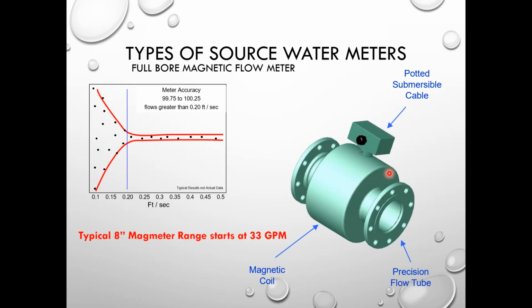So this screen shows our typical mag meter, and these are probably the most popular meter now in the industry. You've got a fixed ID, you've got flanges, the magnetic coil is around the pipe, and it's measuring the velocity via electromagnetic velocity sensor. So the way those work is that the coil creates a magnetic field, and as water passes through a conductor, it produces a small amount of voltage or current that the electrodes read. So the velocity is directly proportional to the current that's built up by the water moving through the conductor.